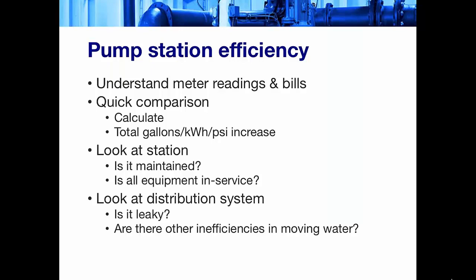So you do that for one pump station and a second pump station, and you can begin to see, oh, to increase 1 psi of pressure, this one takes quite a few fewer kilowatt hours per gallon pumped. So that would be a good way to baseline within your own system which pump station is more or less efficient. There are some things you can also do just by visiting the pump station and looking at the records that have been maintained for that pump station: is the pump station actually being maintained? Maintenance is a very good indicator of the efficiency of operational equipment. If you're doing preventative maintenance per manufacturer schedules, you're much more likely to keep things operating in an efficient manner.